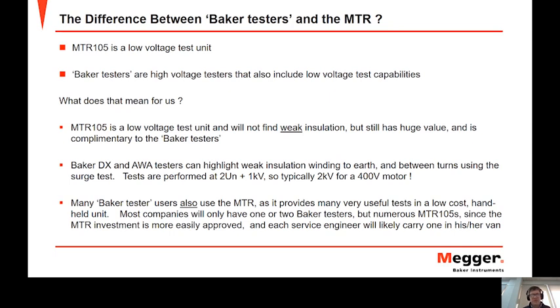So I'm often asked what's the difference between the Baker testers, the Megger Baker testers, and the MTR. So a Baker tester, for those that haven't heard of them before, it's a high voltage multifunction tester specifically designed for testing motors and rotating machinery. It provides IR, PR, PI, DAR, DC step voltage, DC high pot, and also the surge test. And that's used for detecting turn-to-turn and phase-to-phase insulation weakness. The testers can also offer winding resistance using the 4-wire measurement system, and also inductance and capacitance in some units.